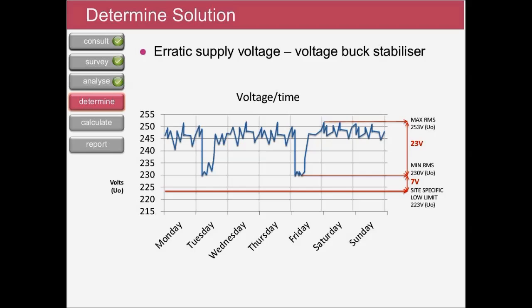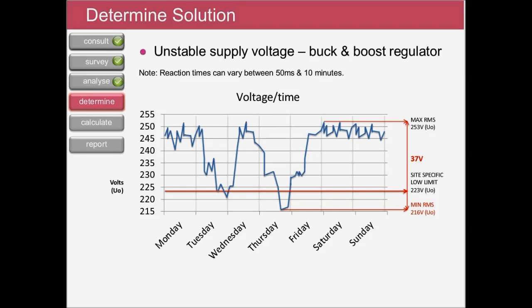Where voltage profiles prove to be more erratic, the opportunities for fixed ratio solutions will begin to diminish. In these applications, voltage stabilizers can sometimes be used, or on-load tap changers. They may prove more viable by reducing and maintaining the output voltage to a predetermined level. In more extreme cases, where the existing voltage profile is already low, for instance during infrequent peak periods, voltage regulators may prove to be the viable chosen solution. By design, these units are capable of bucking and boosting, in other words, decreasing and increasing the voltage to maintain the predetermined set point, even during certain power dips.